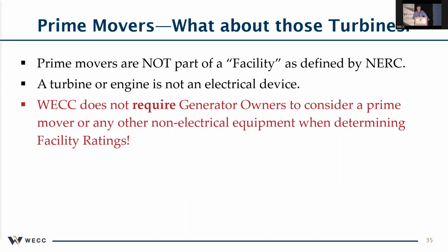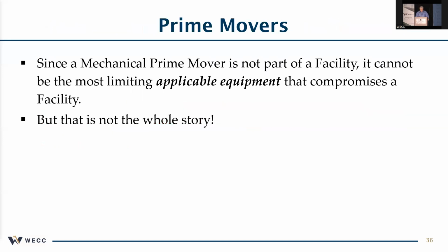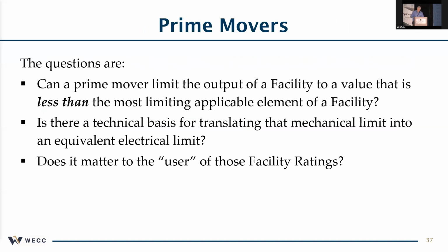WECC will never require you to consider a prime mover or consider any mechanical limit in your electrical facility ratings. If you want to use just the nameplates of the electrical components, that's perfectly acceptable. But what we are saying as an option, realistically, if you do have a prime mover that limits your facility, you may use that providing you have the justification for it. It's not part of a facility, so it cannot be the most limiting applicable equipment that comprises a facility. But that's not the whole story.